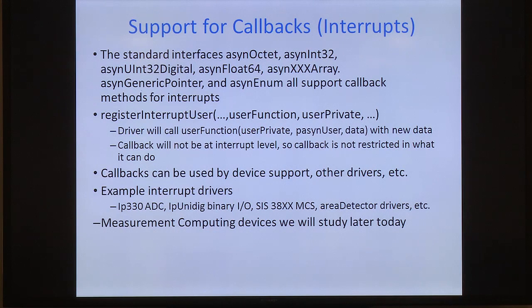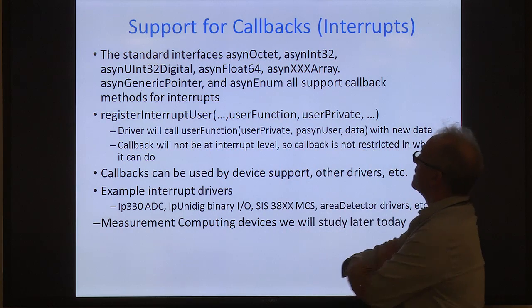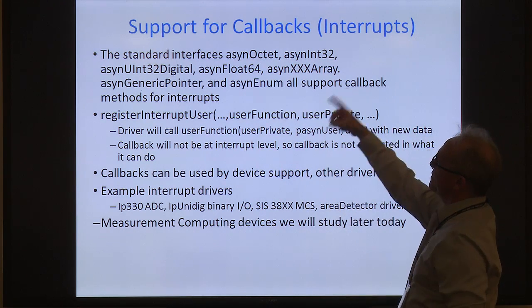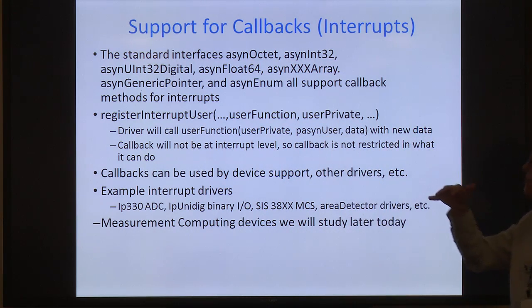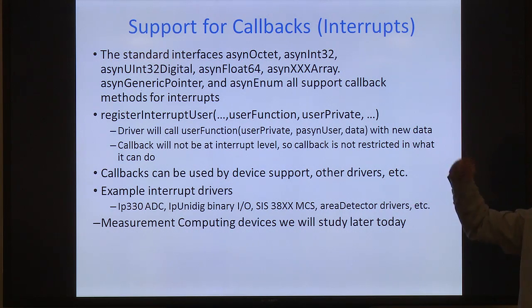Okay, let's talk about support for callbacks, which I've mentioned now briefly. You could also call them interrupts. So all of these standard interfaces support callback methods for interrupts. And as I said previously, these are usually used for input records that have scan equals I/O interrupt, so that the record will update its value asynchronously whenever the driver tells it.